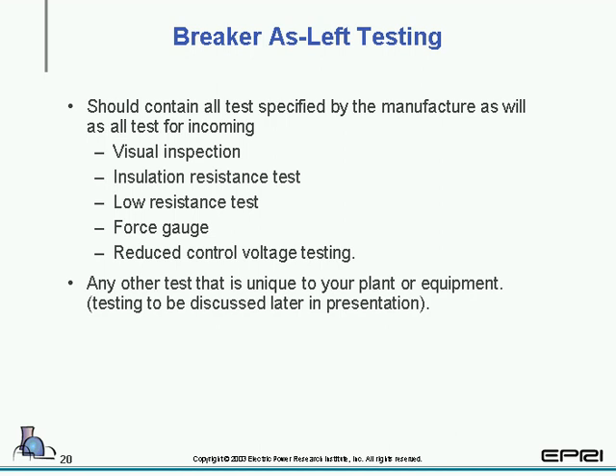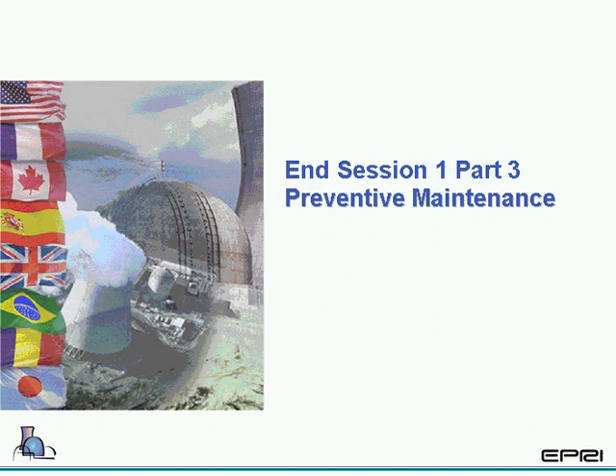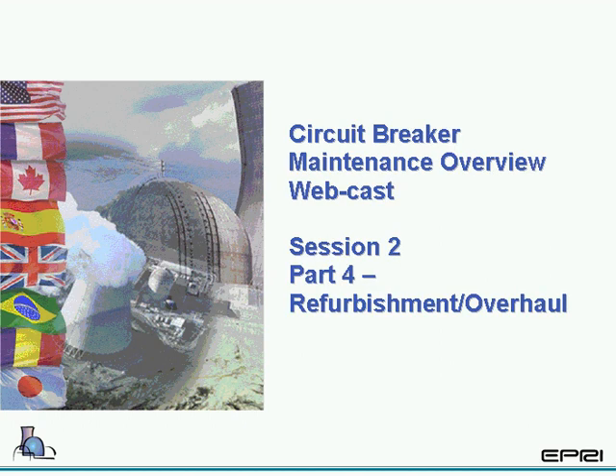Now, beyond the items that we spoke about during incoming testing, you should use the manufacturer's recommendations, as well as any other test that is required by your plant. And the main goal with as-left testing is to verify that the breaker is going to operate, not at that moment, but up until the time you get ready to remove the breaker from the cubicle, to change it out, or to overhaul it again. And that pretty much ends the preventative maintenance. Now what we're going to take a look at is Part 4, refurbishment and overhaul.